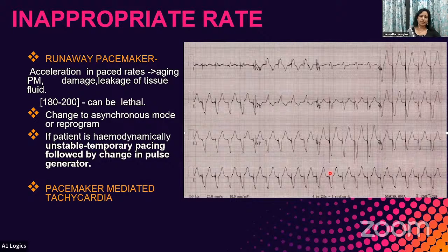But what is the difference between this PMT and runaway pacemaker? In pacemaker mediated tachycardia, usually the rate doesn't go beyond the set rate. Usually they will set a lower rate, for example 60, and a higher rate of 130. Here it doesn't go beyond that 130, but in runaway pacemaker the rate will be very extreme, more than 180, 200. Okay, so this is the pacemaker mediated tachycardia.